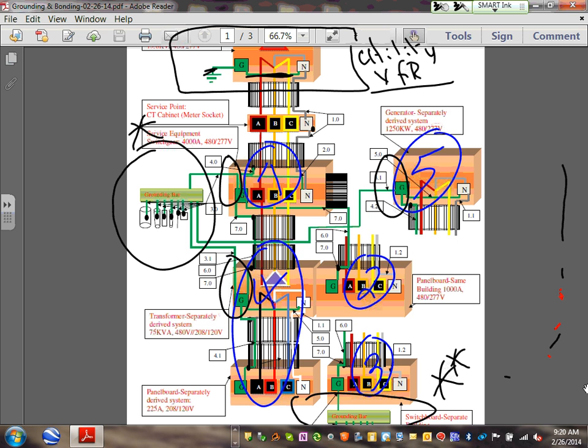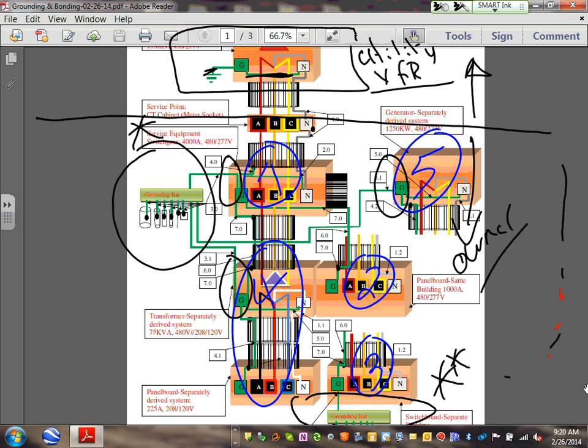The last thing I'm going to show you guys is called the demarcation point right here. From here up is the electrical utility. From here down is owner. Can you guys see that? That's the demarcation point. That's where the utility is responsible, right here at the service point. From here up, that's the responsibility of the utility, maintaining the system, taking care of it. From the service point down, that's our responsibility, grounding and bonding and pulling wires and so on. And we own and operate.